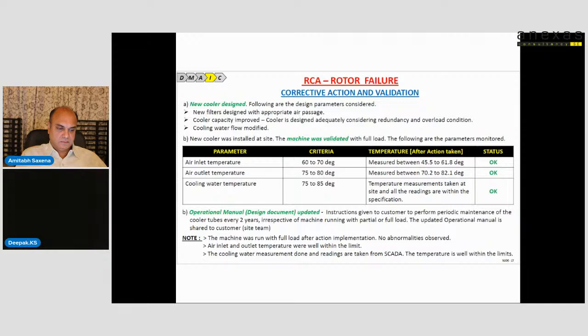The second part is the operational manual. We updated the design document and operational manual, and we instructed the customer to perform the periodic maintenance of the cooler tubes every 2 years, irrespective of the machine running with partial or full load. The updated operation manual is shared with the customer. Finally, the machine was run with full load after action implementation. No abnormalities observed. Air inlet and outlet temperature were well within the limit. The cooling water measurement was done and readings were taken from SCADA. The temperature is well within the limit.